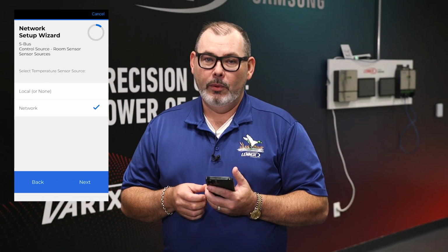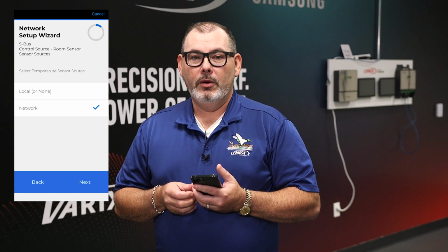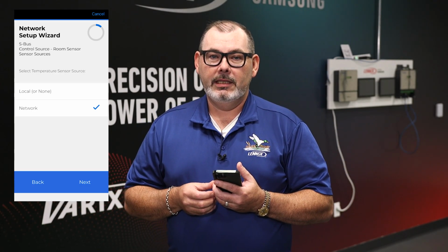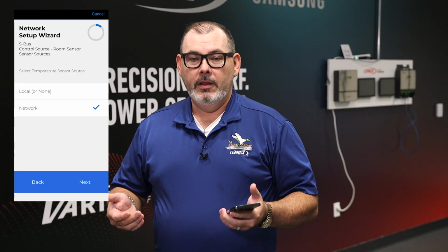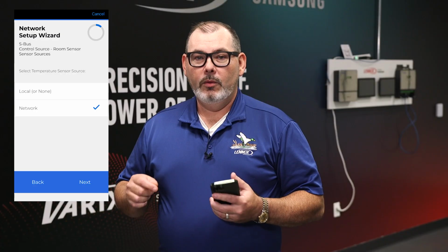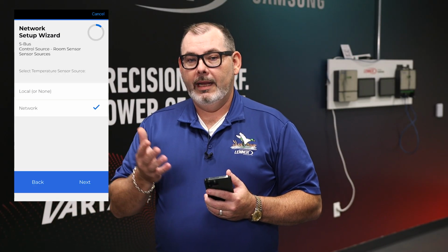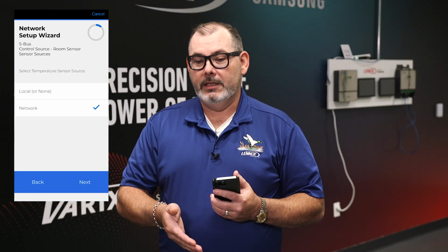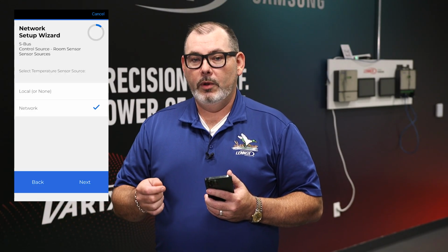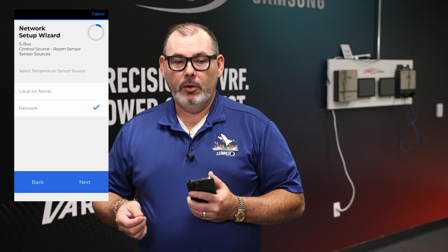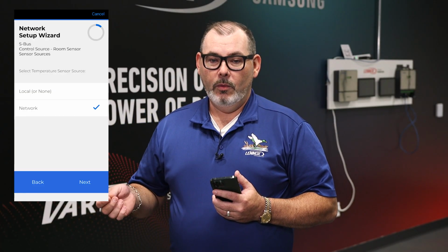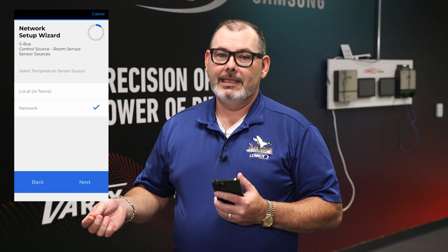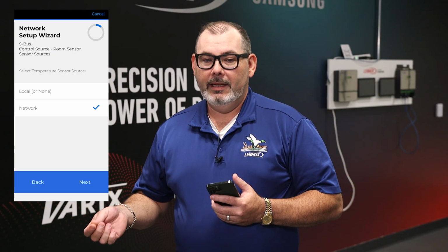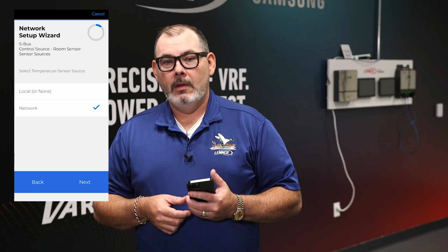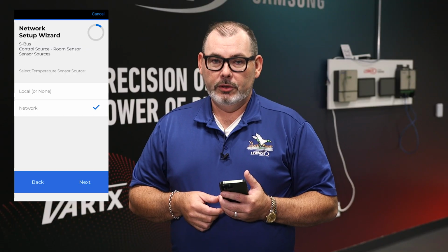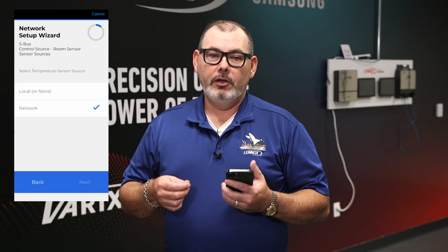Your next selection is very important as well as the other 2. This will be where you're going to set your temperature source. This is where we're actually getting the temperature source for the zone that you're working in. The zone that you're working in will be either coming from your CS8500 or, again, a local mounted zone sensor. If it's coming from a local mounted zone sensor, it will be on your TMP on your orange plug on your core board. If it is coming from your network controller, your CS8500, you will need to select network. It's very important that if you don't make the correct selection, you will get error codes. After you've selected the correct temperature source, we will move forward towards setting your blower selections.